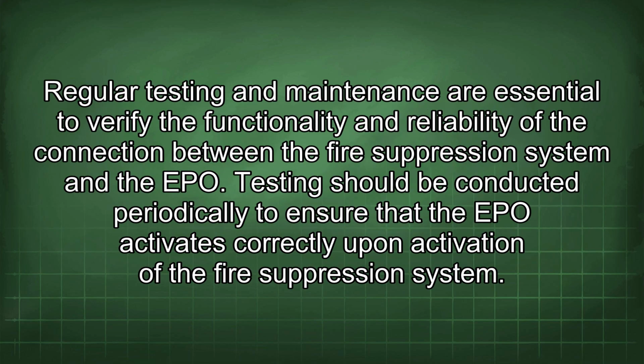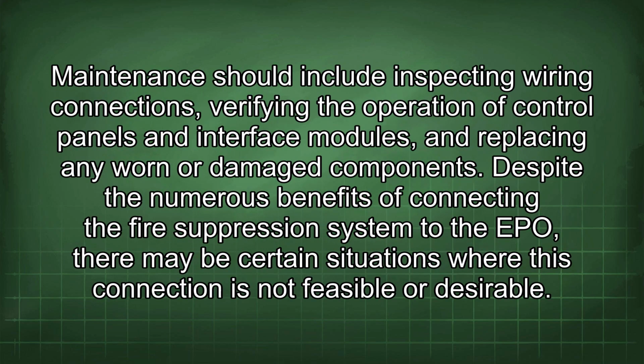Regular testing and maintenance are essential to verify the functionality and reliability of the connection between the fire suppression system and the EPO. Testing should be conducted periodically to ensure that the EPO activates correctly upon activation of the fire suppression system. Maintenance should include inspecting wiring connections, verifying the operation of control panels and interface modules, and replacing any worn or damaged components.